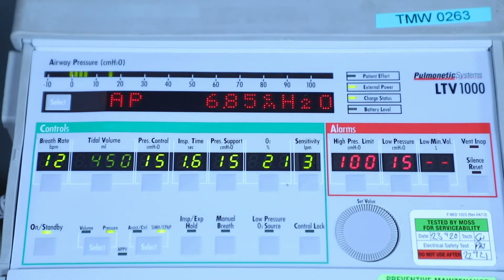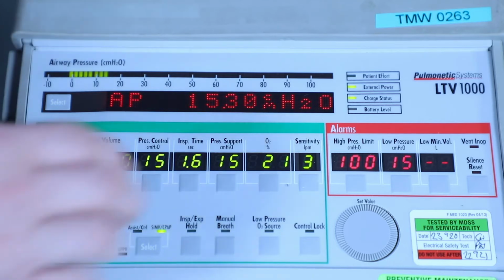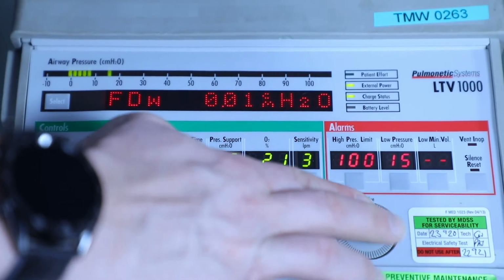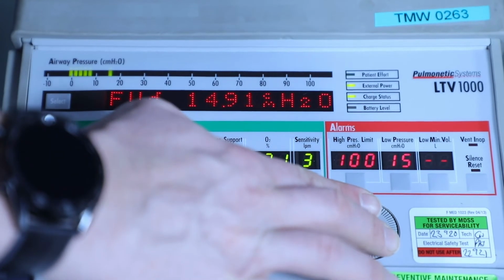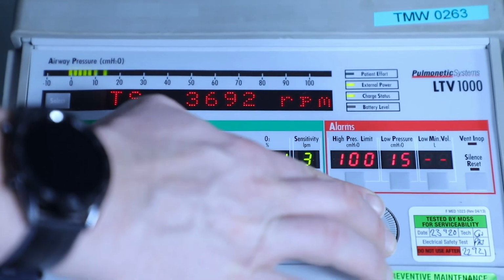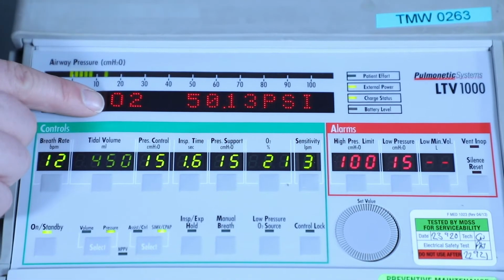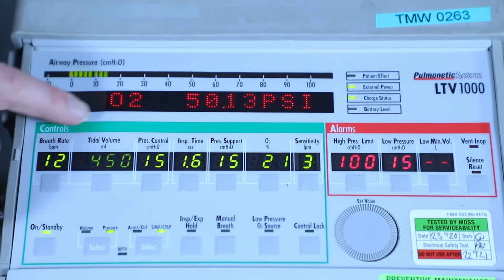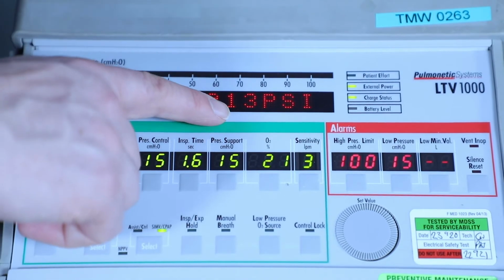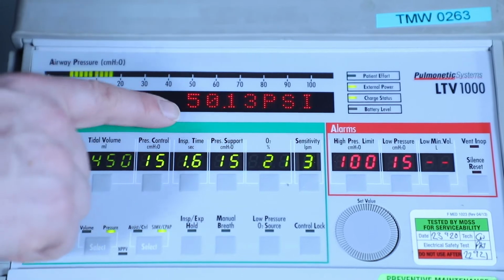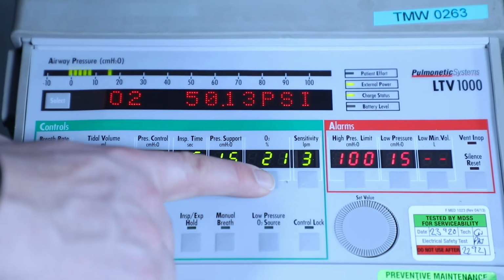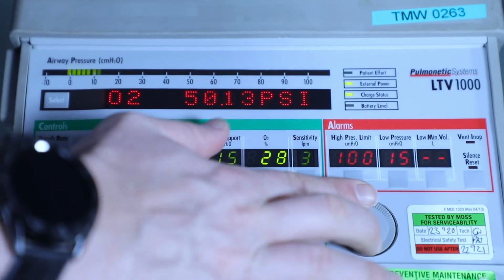First thing we want to check is the O2 PSI. So if we scroll through, we're now on the O2 and this is the PSI. We want to ensure that this number remains between 40 and 80. So to test this, we'll increase the oxygen to approximately 40%.